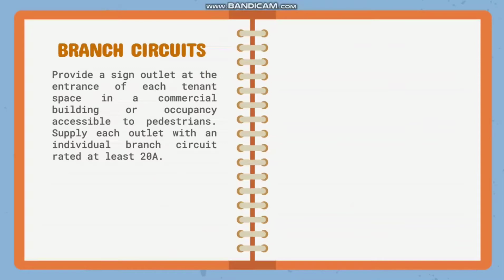So, branch circuits provide a sign outlet at the entrance of each tenant space in a commercial building or occupancy accessible to pedestrians. Supply each outlet with an individual branch circuit rated at least 20 amperes. So, first thing na manonotice natin kapag pupunta tayong strip malls and other commercial buildings is merong signs every store. So, naglalagay ng signs for several reasons, including the fact that every commercial occupancy needs a form of identification, and the standard method is the electric sign.